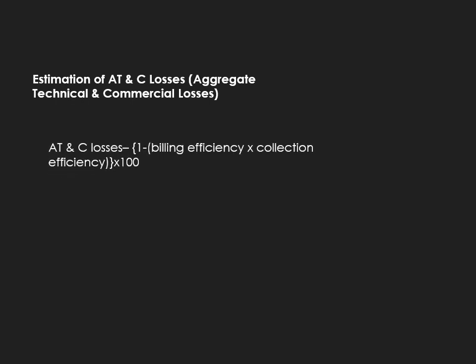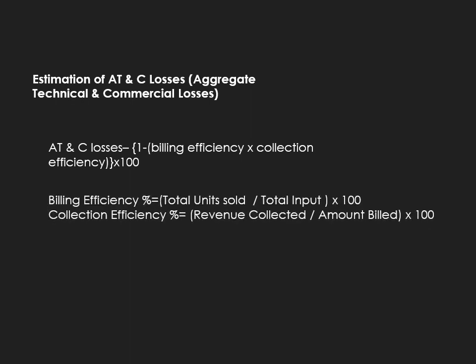This is an important formula for estimation of AT&C losses — Aggregate Technical and Commercial losses. Questions have come on this formula many times. The formula is: AT&C losses = (1 − billing efficiency × collection efficiency) × 100. Billing efficiency (%) = Total units sold / Total input × 100. Collection efficiency (%) = Revenue collected / Amount billed × 100. These formulas are helpful for both objective type and short answer type questions.